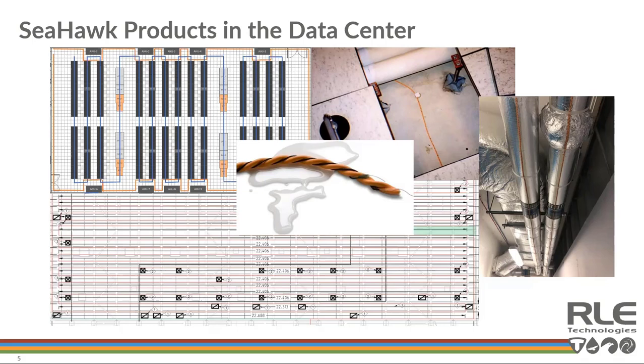But the other thing is that the leak detection systems, we've designed them to eliminate false alarms, and that's a real driving factor. Other cables on the market are going to be more prone to nuisance and false alarms because they have conductive jackets on their sensor wires, and a little dirt or dust over time might bridge those sensor wires and create an alarm condition. Whereas when you look at the picture here, you actually have a non-conductive polymer mesh that the fluid has to leach through, bridging through the twist of the cable to the next sensing wire, before an alarm condition occurs. So it's really designed to eliminate false alarms, and that's a big part of the success of the leak detection.